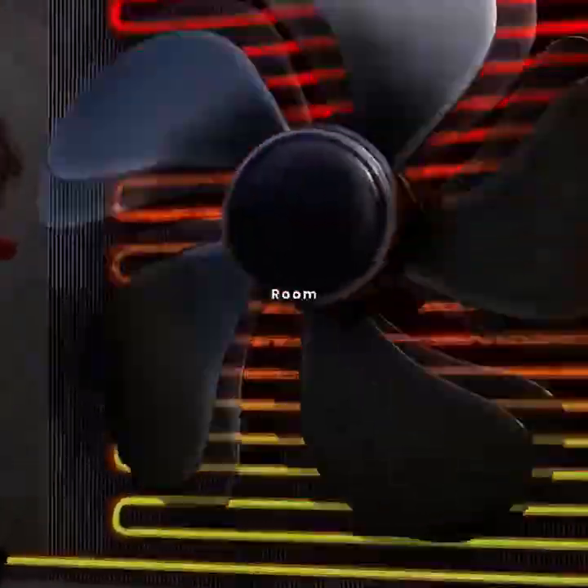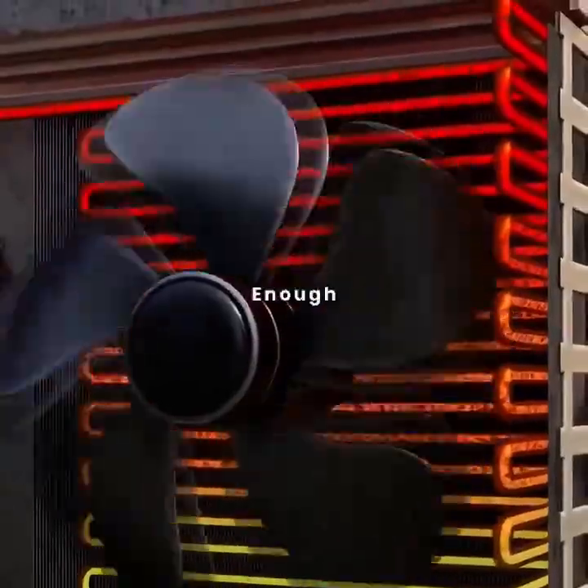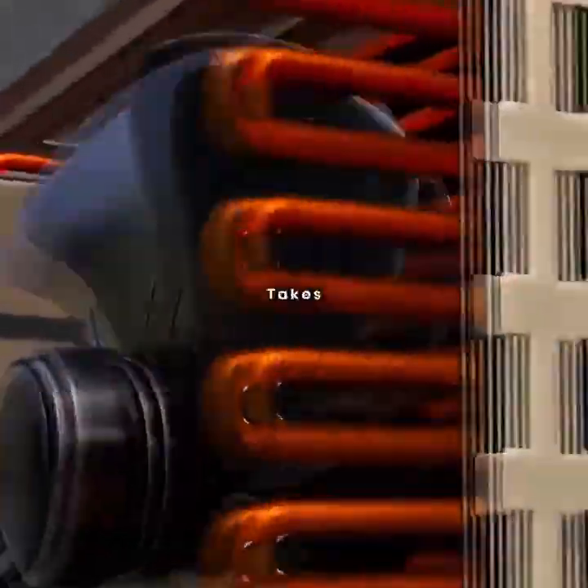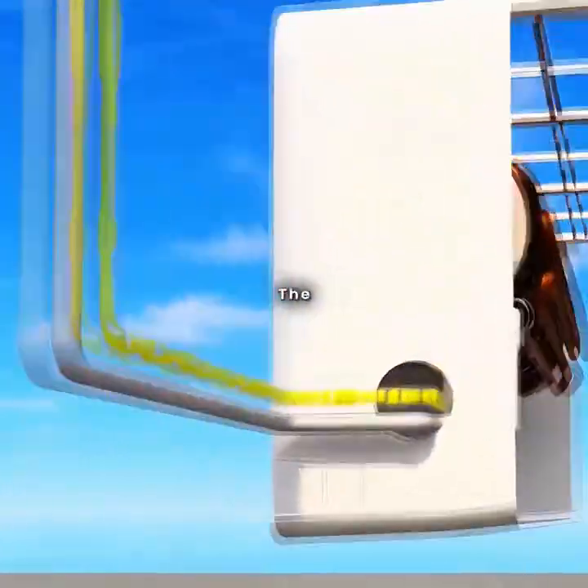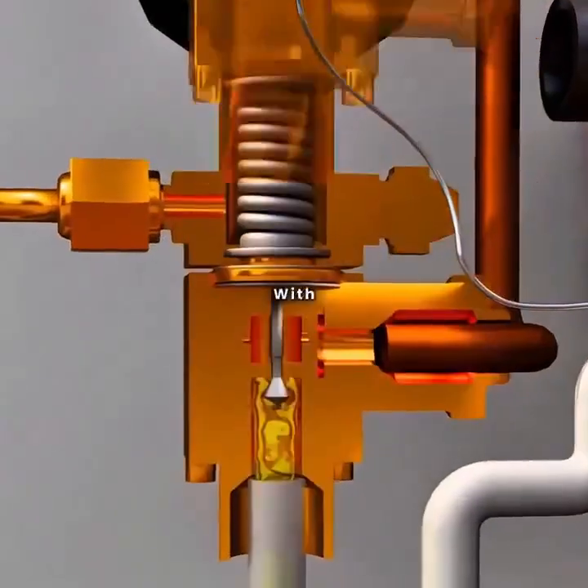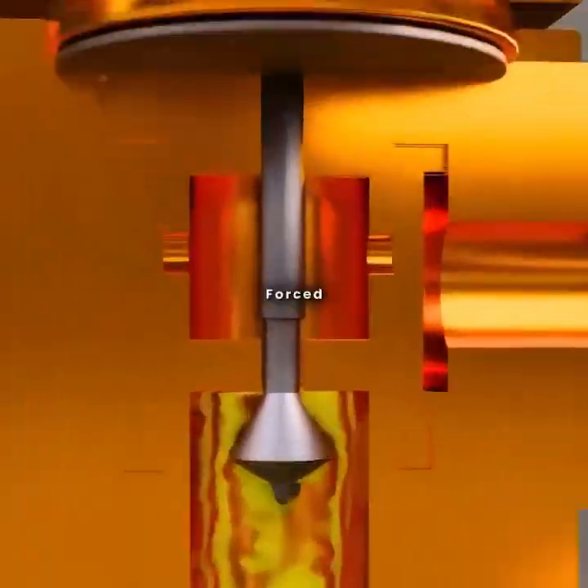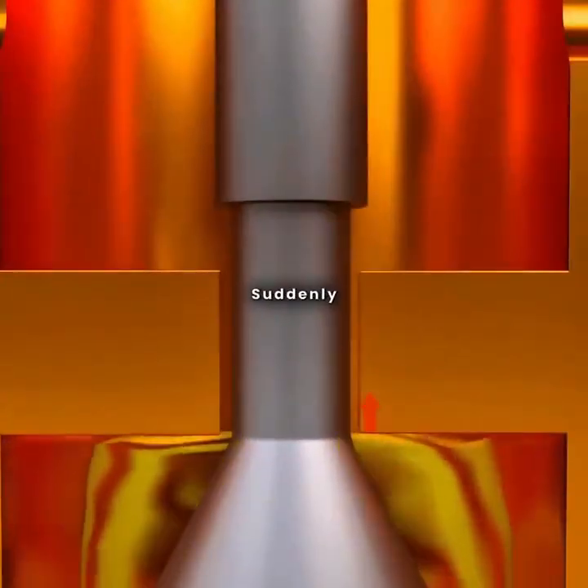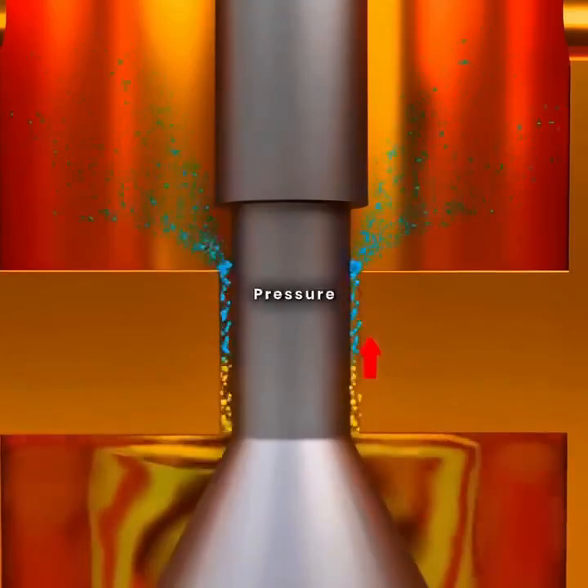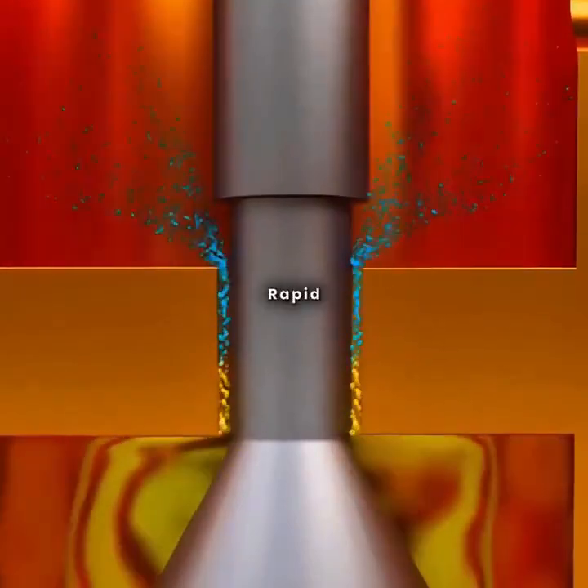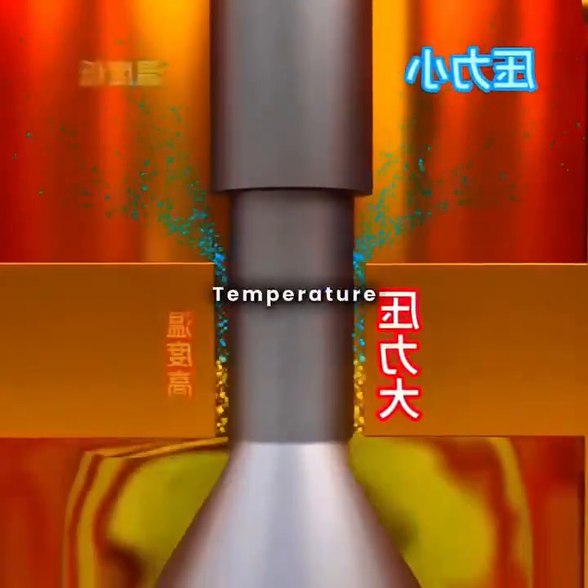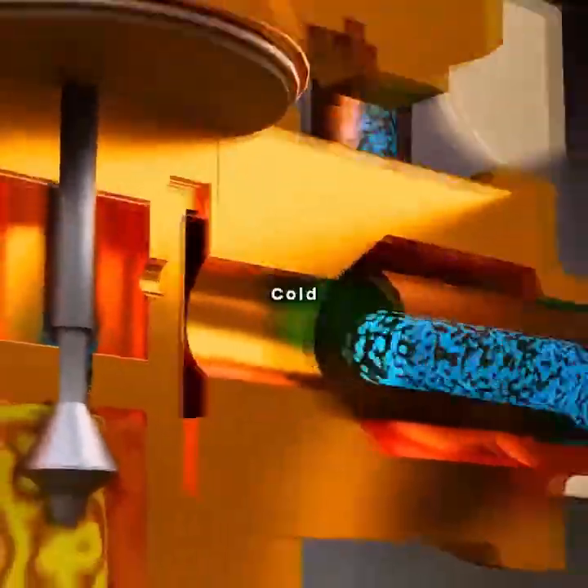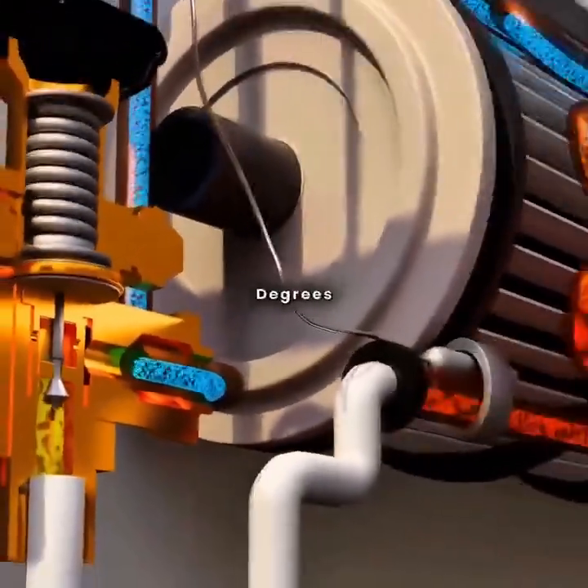However, 50 degrees Celsius is still much too warm to cool a room. So how does the refrigerant become cold enough? This is where the most important step takes place. The liquid refrigerant enters the expansion valve, which acts like a faucet with a tiny opening. As it is forced through the narrow passage and suddenly enters a much larger space, its pressure drops dramatically. With that rapid pressure drop comes a sharp drop in temperature. In an instant, the 50 degrees Celsius liquid becomes a cold mist at below 7 degrees Celsius.